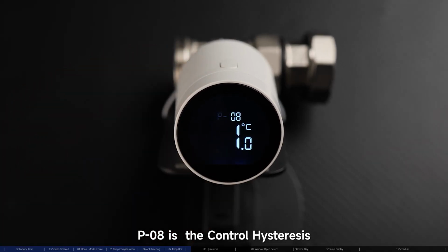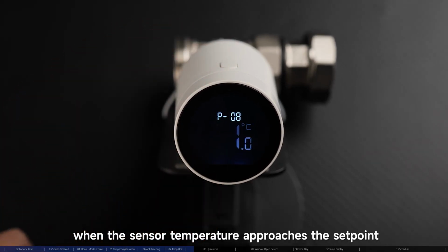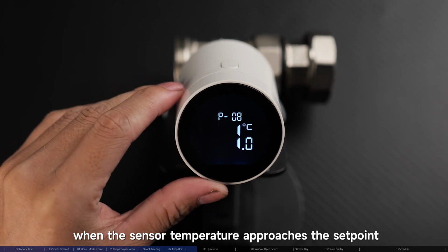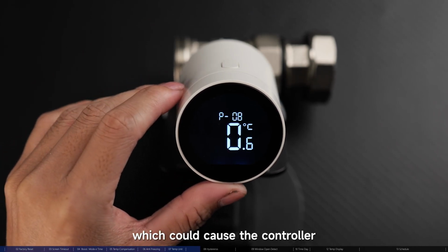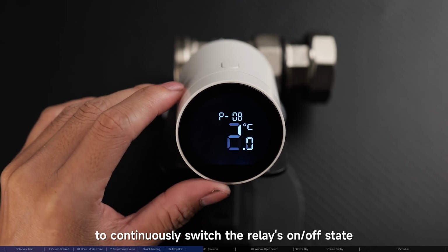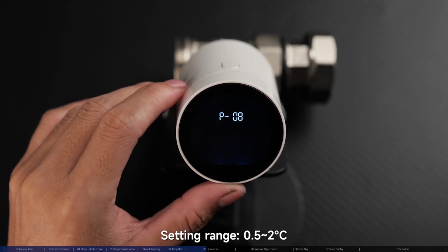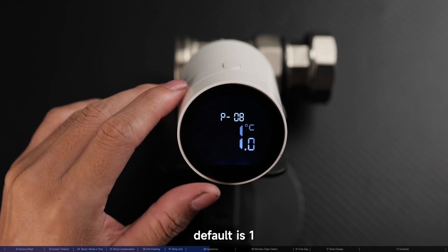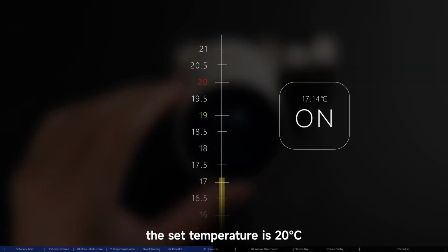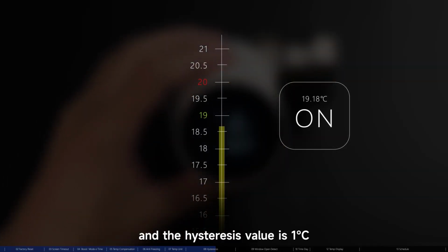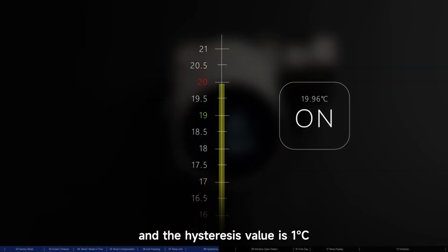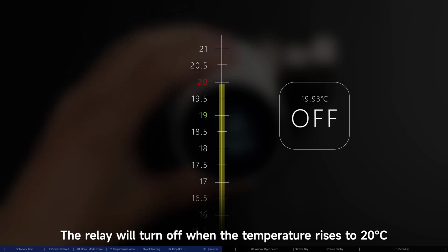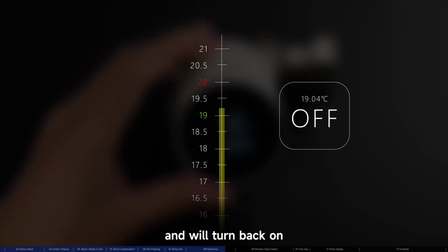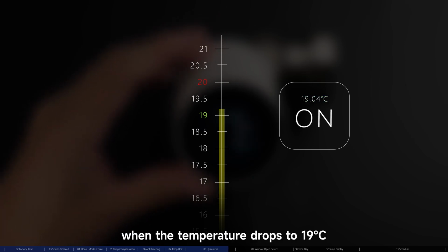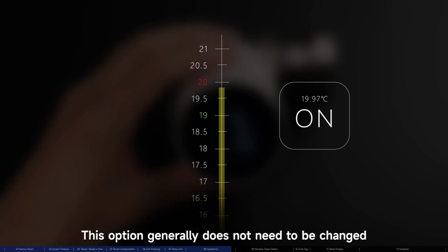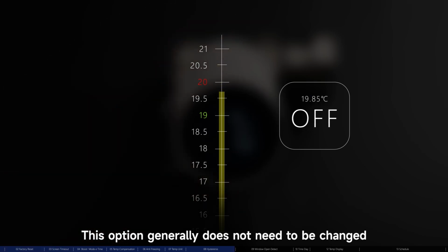P08 is the control hysteresis. To prevent fluctuations when the sensor temperature approaches the set point, which could cause the controller to continuously switch the relay's on-off state. Setting range 0.5 to 2 degrees Celsius, default is 1. For instance, the set temperature is 20 degrees Celsius and the hysteresis value is 1 degree Celsius. The relay will turn off when the temperature rises to 20 degrees Celsius and will turn back on when the temperature drops to 19 degrees Celsius. This option generally does not need to be changed.